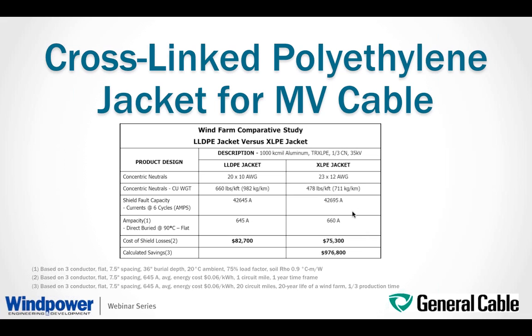Here I'm showing a quick comparison, picking one of the larger sizes used in the wind farm collector system. It is based on a 1,000 kcmil aluminum TRXLPE 35 kV cable with a 1/3 neutral. We're comparing that 1/3 neutral to a 20 number 10 neutral with an XLPE jacket, looking at the copper content and the shield fault current. With an XLPE jacket, you can optimize your concentric neutral while maintaining the same shield fault current capability, and as you can see, the reduction in the amount of copper in the neutral is significant. There's also a small positive impact on the ampacity of the cable.